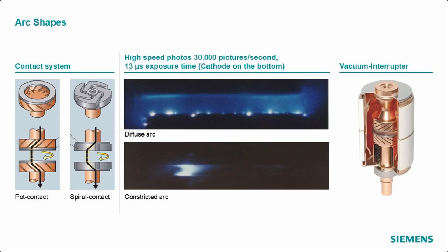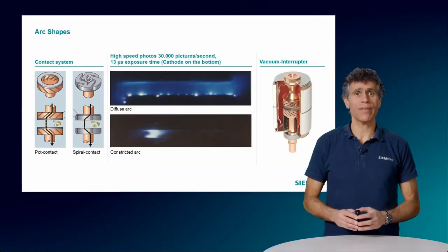By designing the vacuum interrupter chamber and using the principles of magnetic fields, in both cases, the control of the arc and its movement prevents any hot spot or melting of the contacts, ultimately leading to the arc's extinction at the current zero crossing. Managing such design and the characteristics of the arc is crucial for the effective and safe interruption of the current flow and for ensuring an extremely long service life.